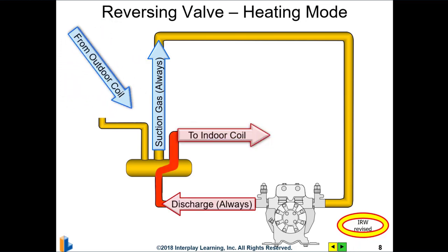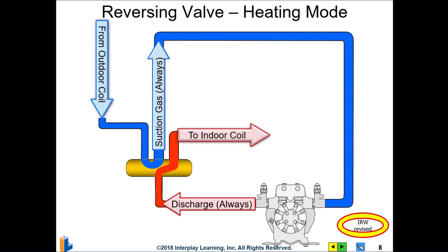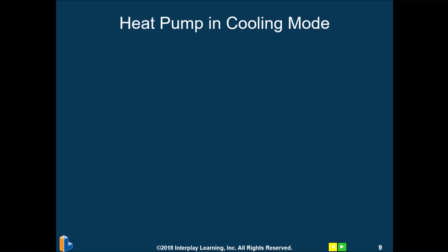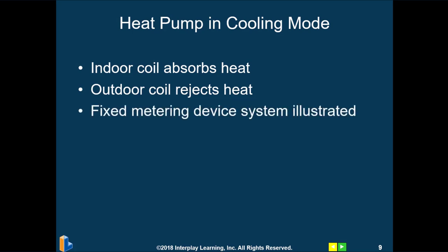In the heating mode, we have suction gas coming from the outdoor coil into the valve port and back to the compressor. The discharge gas goes to the indoor coil, where it can reject heat and heat the space. In cooling mode, the indoor coil is absorbing heat and the outdoor coil is rejecting heat, just like any other air conditioning system.